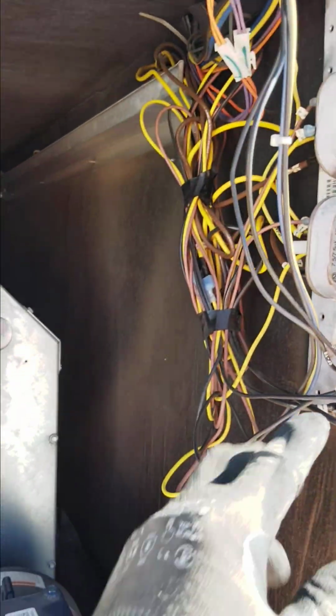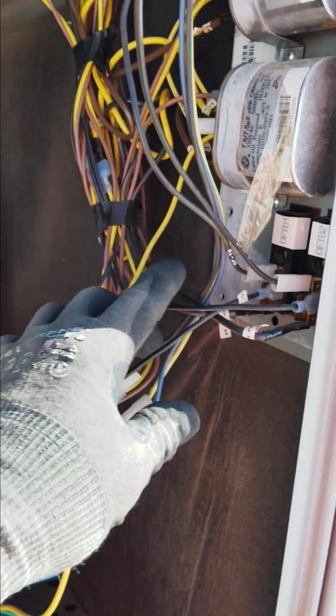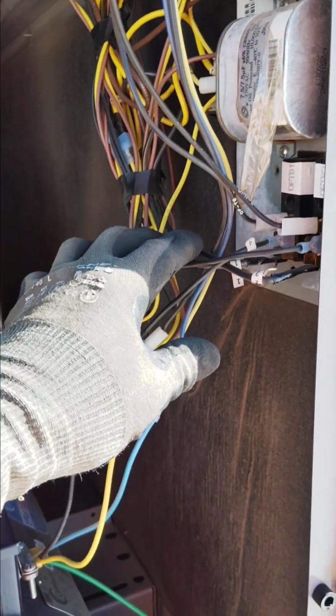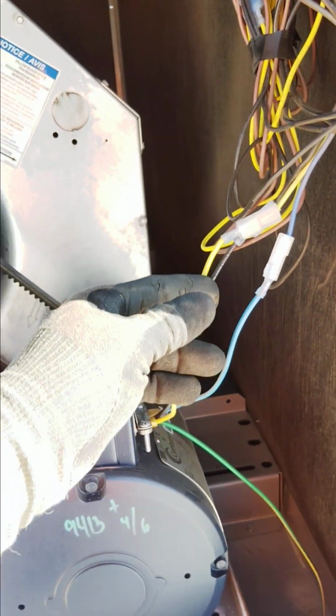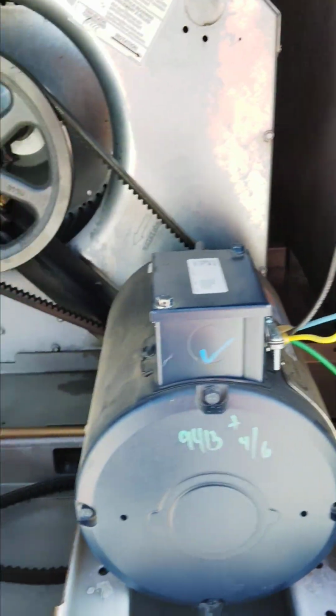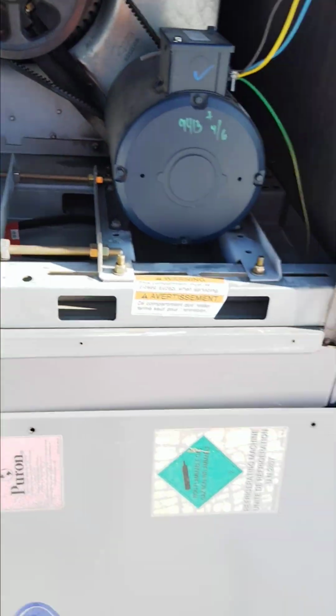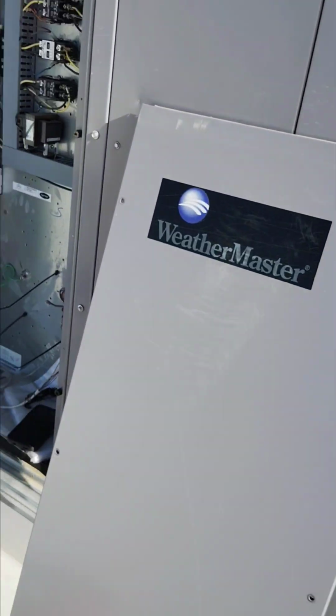We have high voltage coming in, going into a block, and then all the condenser wires are connected here, each leg to the condenser, and then you have the blower motor, and that's a housing right there with a belt. So we're gonna check the amperage on each leg for that motor, and then here you have a compressor on one side, stage 1, and the stage 2 compressor is on the other side.